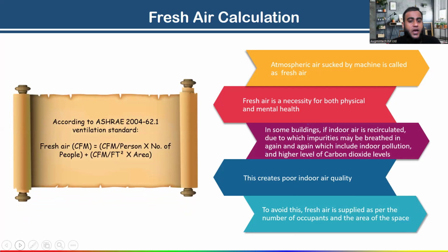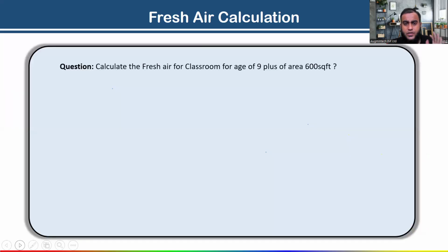So according to the ASHRAE 2004 62.1 ventilation standard, to calculate the fresh air CFM, the formula is written here. Can you see? CFM per person means outdoor air per person, multiplied by the number of people, plus CFM per square feet multiplied by the area. By using this formula, you can easily calculate the fresh air CFM. Now I will take one example so you will understand easily.